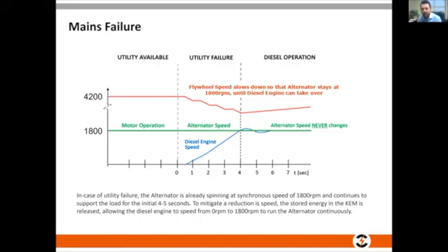You start the ignition, it's on. But it does take time for the turbo lag to stabilize. It takes time for everything to stabilize. So after 4 seconds, maybe you'll start to introduce load, but really after 5 seconds, when the turbo lag has gone, you can put 100% load on the engine, you shut the clutch, and then of course the engine is driving the alternator, it's a diesel generator, that flywheel will speed back up and it will get to this 4200 RPM mark and it will just stay charged.